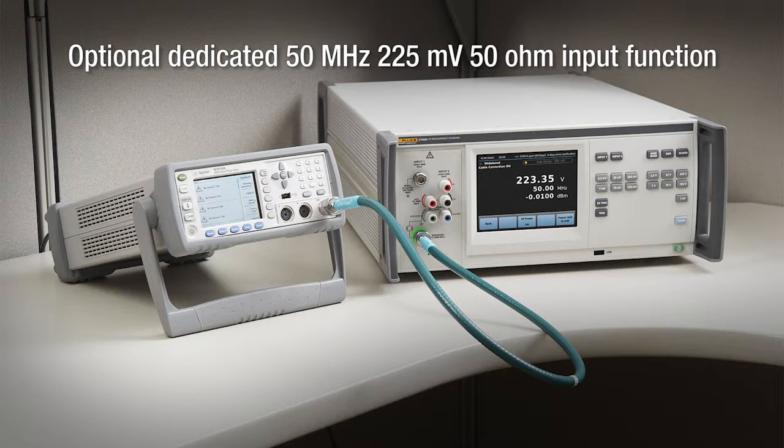The option is spot calibrated at the end of a precision level or phase stable metrology grade cable. It calculates the measured power with 50 Ohm load.